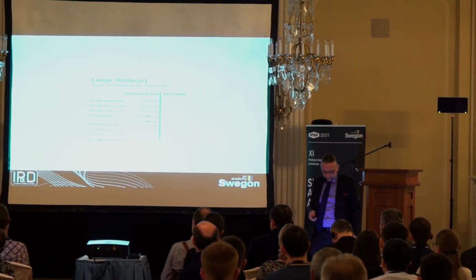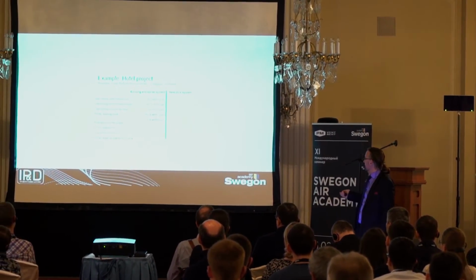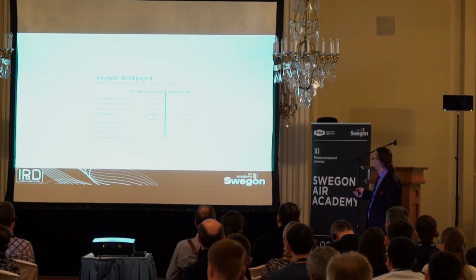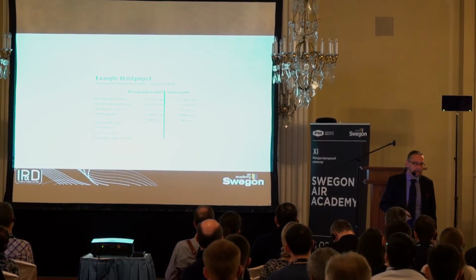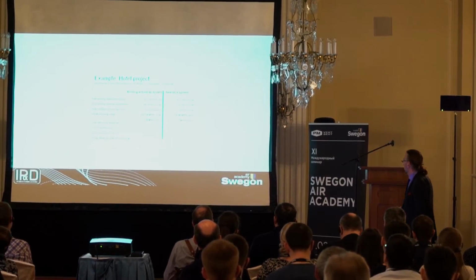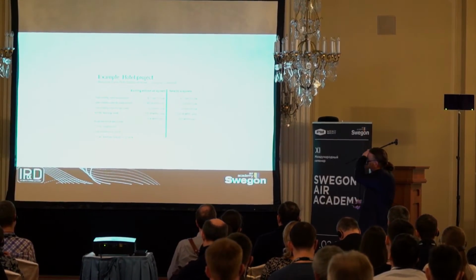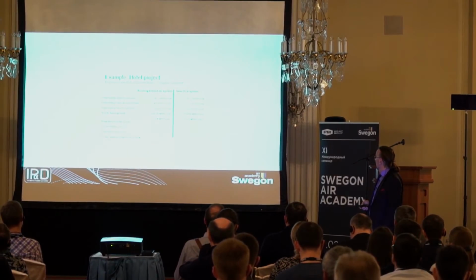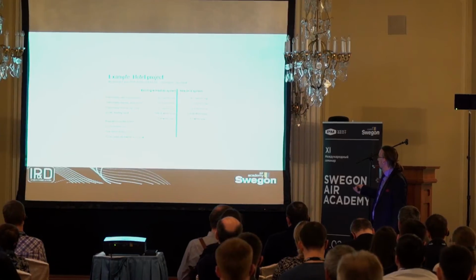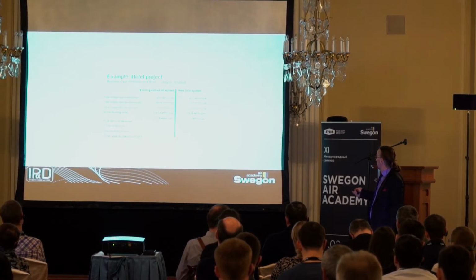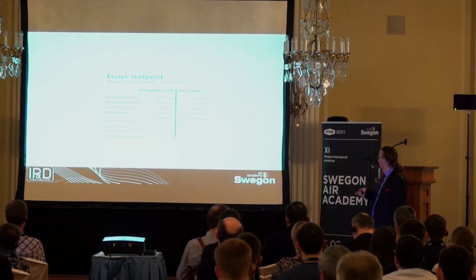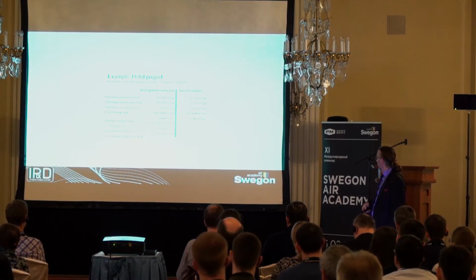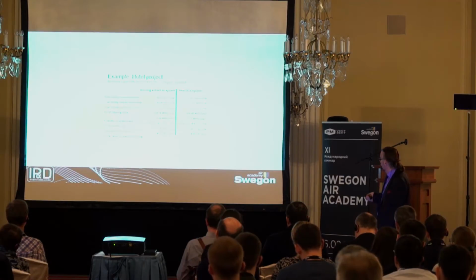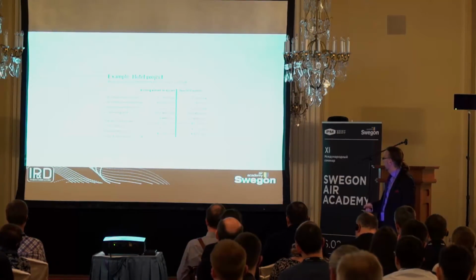Here are the numbers: total heating need was 500 megawatt hours per year for the whole hotel, now it's 116 megawatt hours per year. On the cooling side, there was none before, so now cooling is essentially free. Transmission is the same since we didn't change the building, and tap water heating is the same. But the total heating cost goes from gas to electricity via heat pump, and the energy bill goes from 33,000 euros per year to 9,000 euros per year, down to one third of what it was.